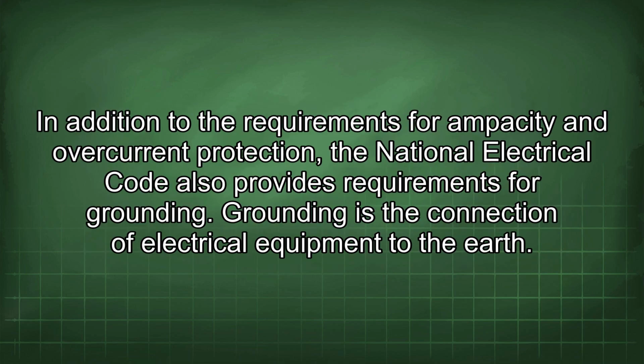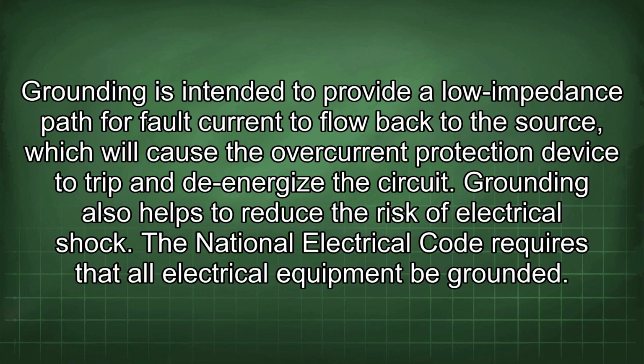In addition to the requirements for ampacity and overcurrent protection, the National Electrical Code also provides requirements for grounding. Grounding is the connection of electrical equipment to the earth. Grounding is intended to provide a low impedance path for fault current to flow back to the source, which will cause the overcurrent protection device to trip and de-energize the circuit. Grounding also helps to reduce the risk of electrical shock.